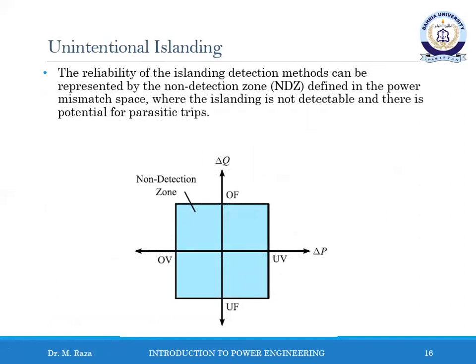The reliability of the islanding detection method can be represented by the non-detection zone, which is called NDZ, defined in the power mismatch space where the islanding is not detectable and there is potential for parasitic trips. An example of a passive detection method is illustrated here. UF and OF stand for under and over frequency, and UV and OV stand for under and over voltage. In the passive detection method, voltage and frequency monitoring of the distribution grid is typically performed in order to trip the inverter in case of under voltage, over voltage, under frequency and over frequency protection. The worst case of islanding detection is represented by the condition where the active power and reactive power are balanced, in which there is no change in the amplitude or frequency.